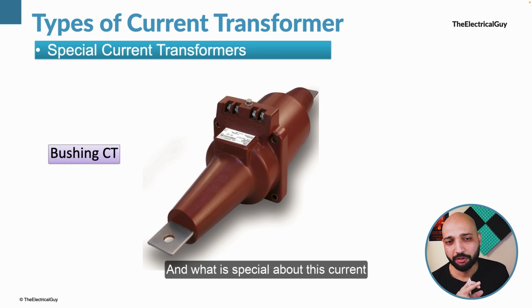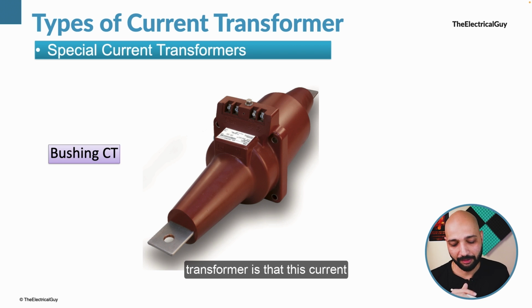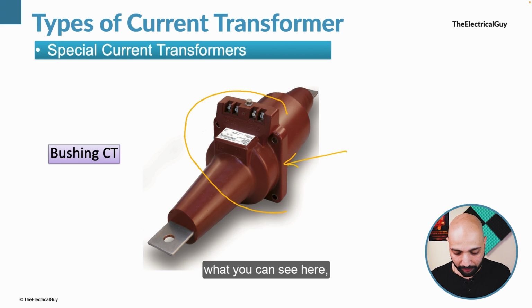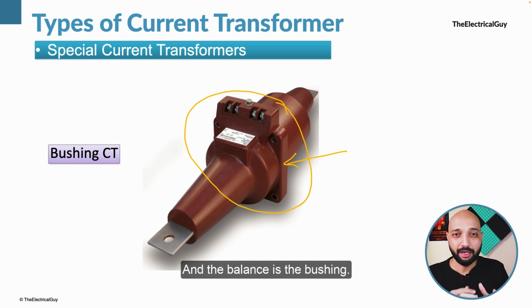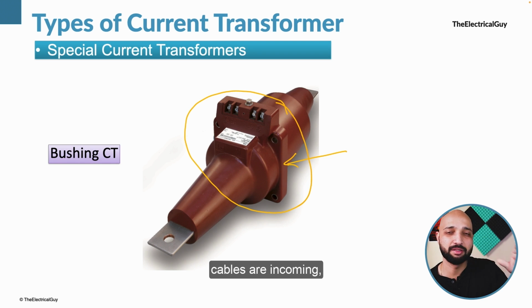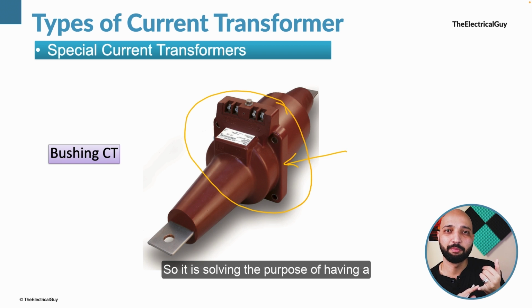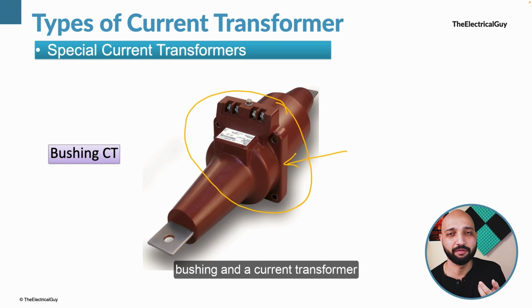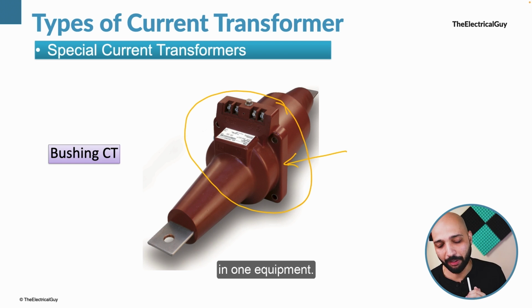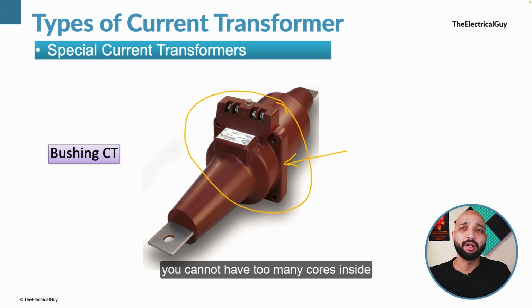What is special about this current transformer is that it is fitted directly inside the bushing. So the center part, what you can see here, is basically a current transformer, and the balance is the bushing. The advantage is that if the cables are incoming, you can simply use this bushing. It is solving the purpose of having a bushing and a current transformer in one equipment. But the problem is that you cannot have too many cores inside this because of the size limitations.